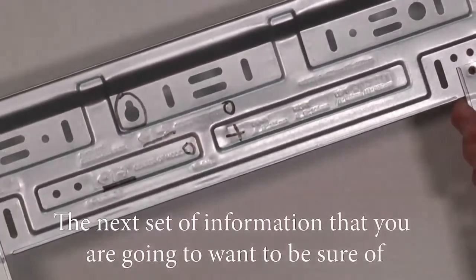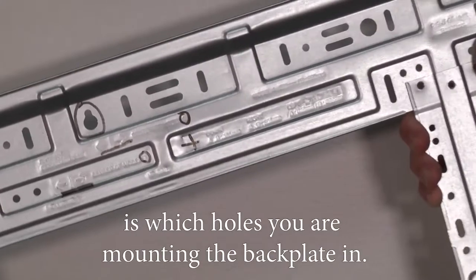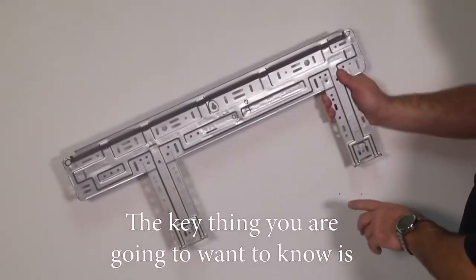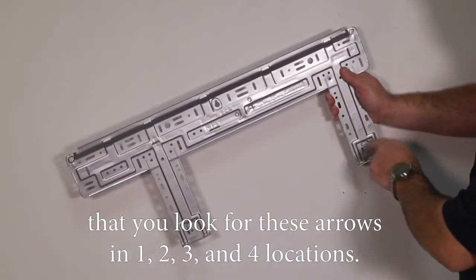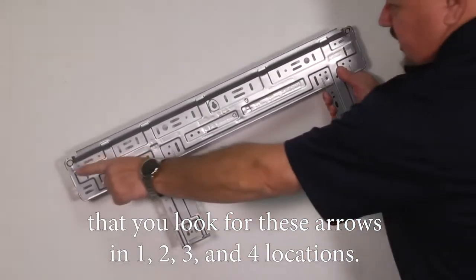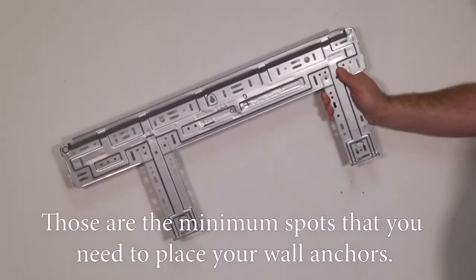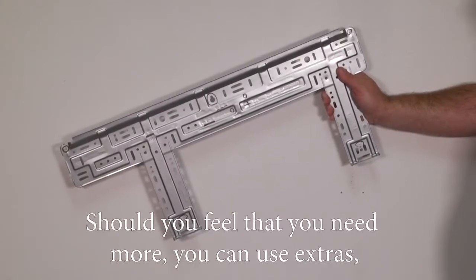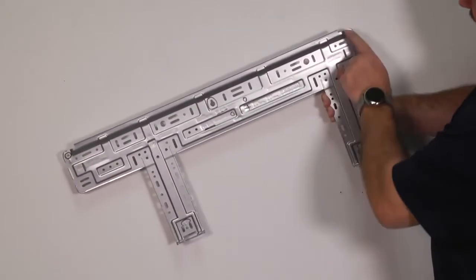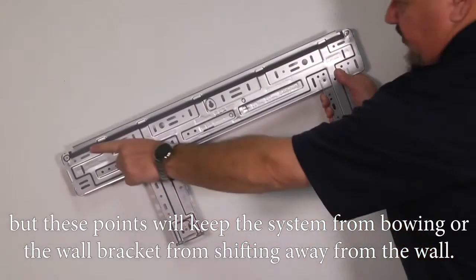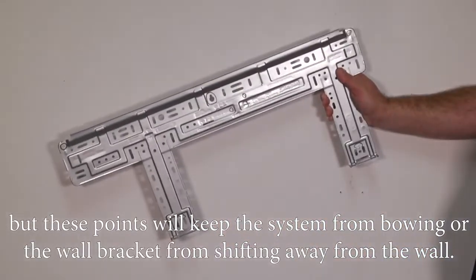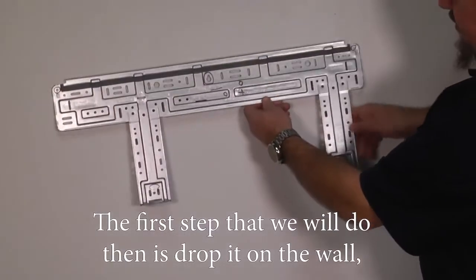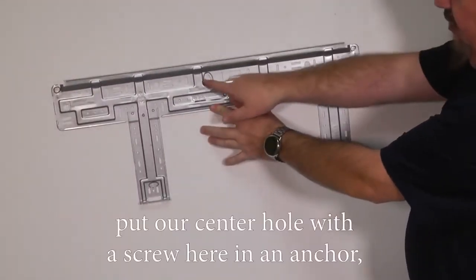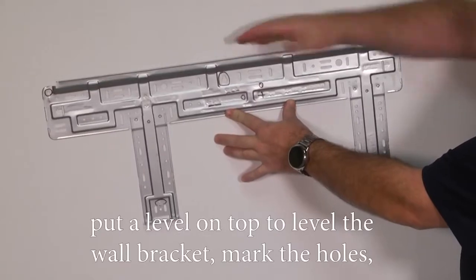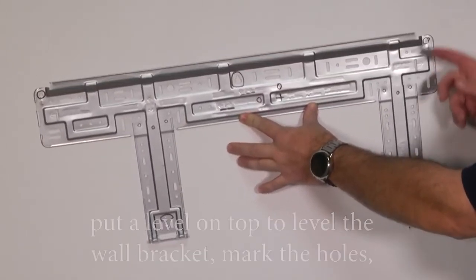The next set of information that you're going to want to be sure of is which holes you're mounting the back plate in. The key thing you're going to want to know is that you look for these arrows in 1, 2, 3, and 4 locations. That's the minimum spots that you need to place your wall anchors. Should you feel that you need more, you can use extras, but these points will keep the system from bowing or the wall bracket from shifting away from the wall. The first step that we'll do then is drop it on the wall, put our center hole with a screw here and an anchor, put a level on top to level the wall bracket, mark the holes, and install the anchors in the proper location.